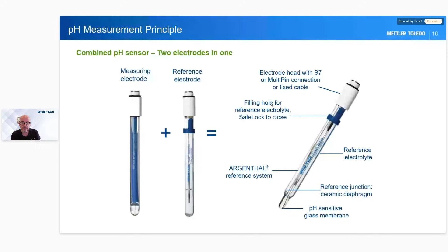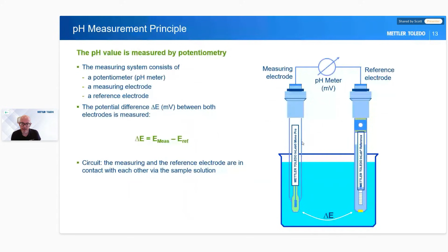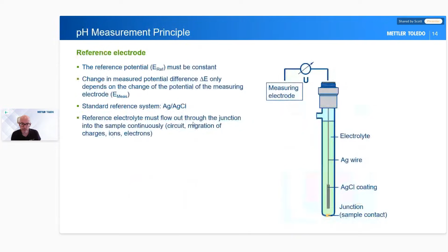So the last little bit of what we did, a couple of slides back, I showed you just quickly. This part here is where we measure the potential difference between these two electrodes. It isn't straightforward maths of minusing one from the other. What we actually have is another part of the equation that's shoved in, and it's called the Nernst equation. And this bit takes the measured and the reference potential that I've just talked about, but it also adds a universal gas constant, a temperature and a Faraday constant.